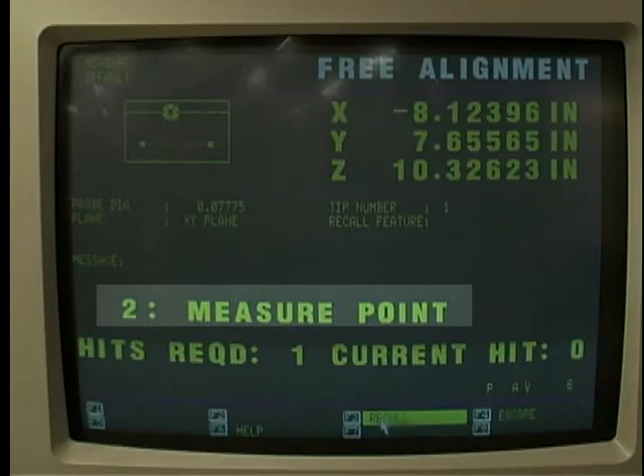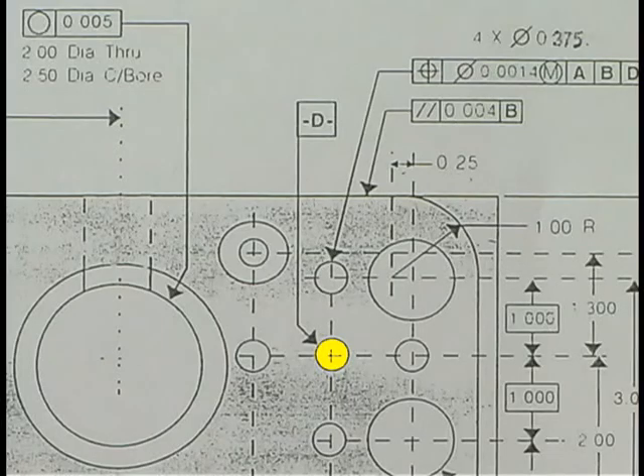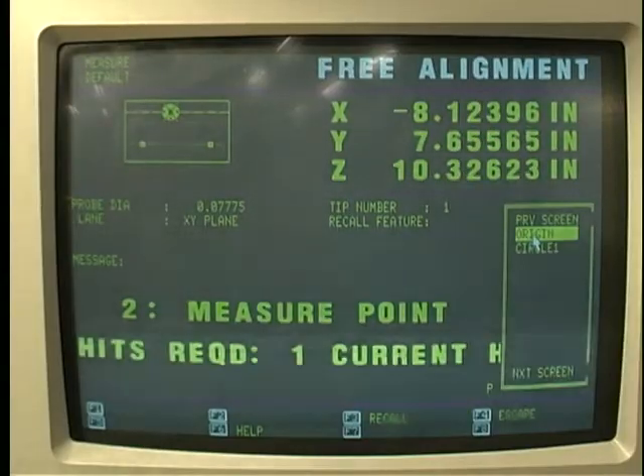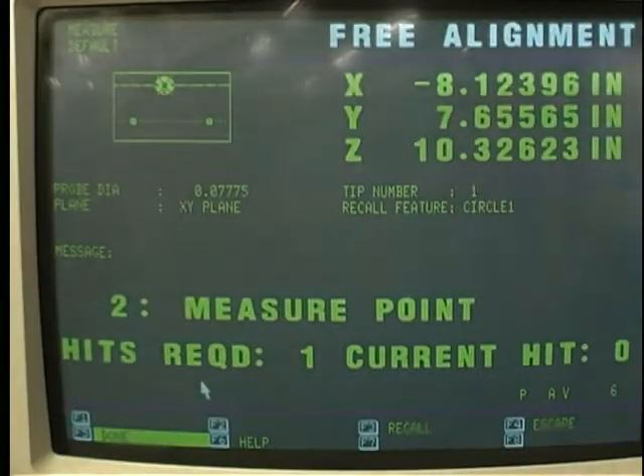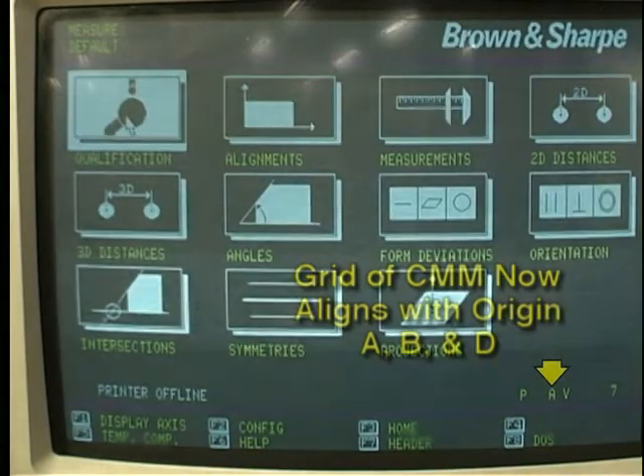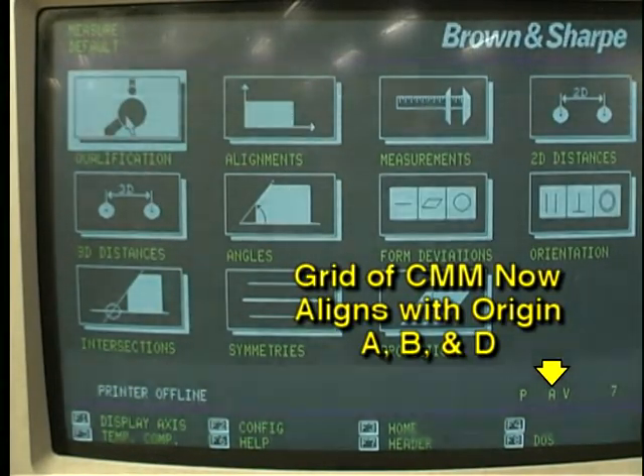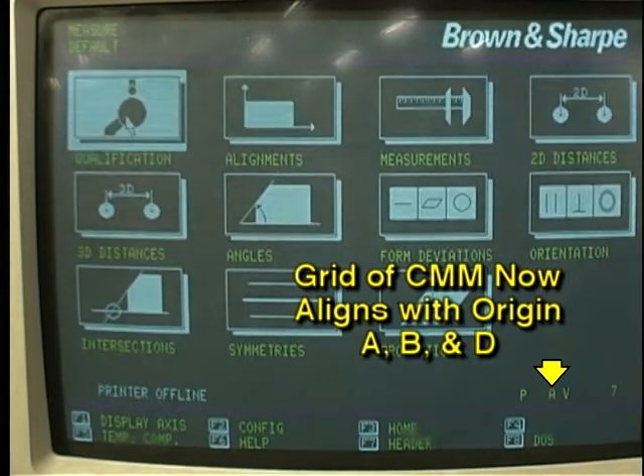Then the computer asks for a point. This is the center point established by touching off inside the hole, which represented datum D. Click recall. Click on circle 1. Then click done. The origin of grid system created by the intersection of datum A, B, and D has now been entered into the computer as the origin of the CMM's grid system.